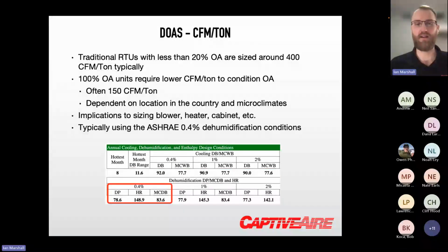If we're looking at a 100% outside air unit, depending on what part of the country we're in, obviously the Southeast, being a hotter and more humid climate than other locations, runs a much lower CFM per ton. So it's very dependent on location. When we're working up selections, we're always going to ask you for the job site location, and we'll pull in the ASHRAE weather data in our selection software just to verify.